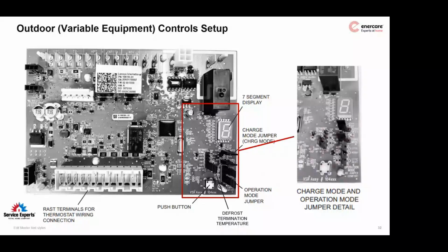A quick note on the outdoor unit here. Let's go through this variable thing real quick because I want to make sure we cover it off. Not terribly often, I think you're going to see this, but if you do happen to see some of these variable units during startup, when you're using a fully communicating control like the S40 or a traditional 24-volt thermostat, the RAST connectors that are shipped with the equipment need to be connected to the terminal here on the bottom left that you can see highlighted in green. There's actually 2 connectors that sit in that single block. Please make sure that they're left there.